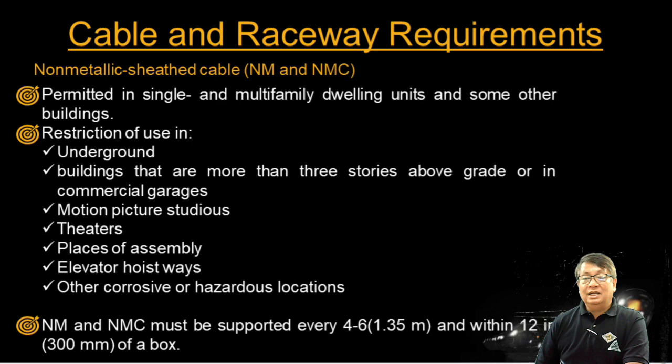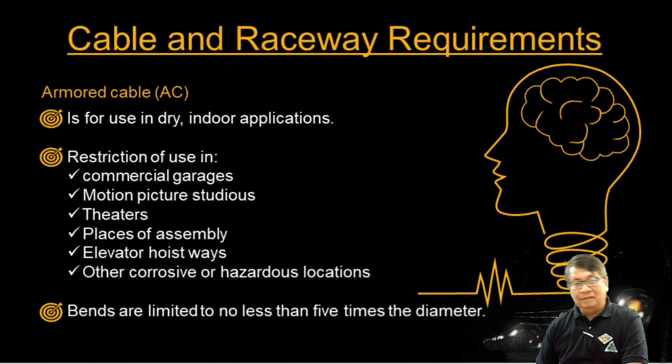And also for armored cable, it is used in dry indoor applications. Restrictions for use are commercial garages, motion picture theaters, places of assembly, elevator hoistways, and other corrosive or hazardous locations. Bends are limited to no less than 5 times the diameter.